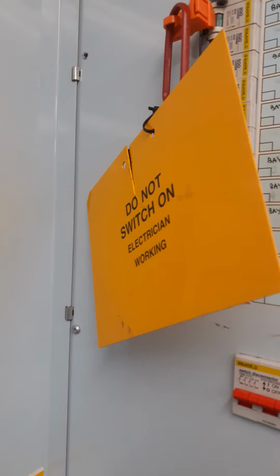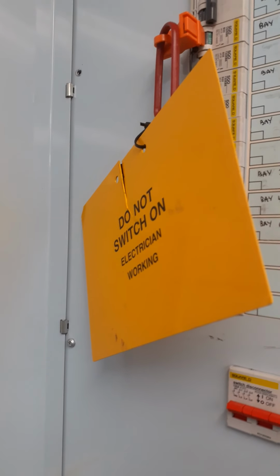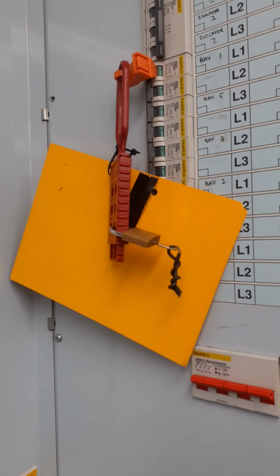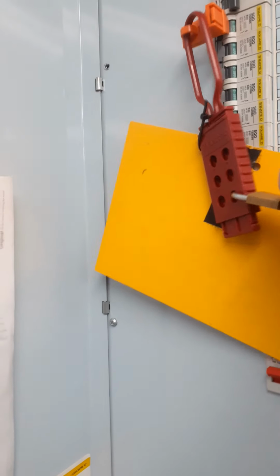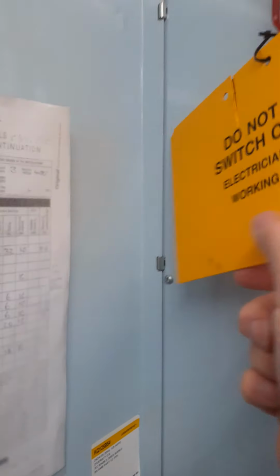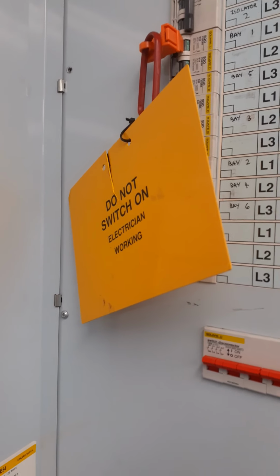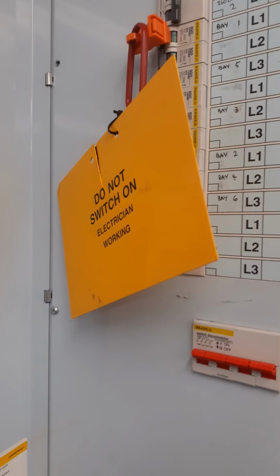The multi-lock then has to be closed. Close the multi-lock like so. A sign is then added through the multi-lock, so to warn everybody not to switch the circuit on, and then each person working on the circuit adds their own lock. So the lock is then fitted, and then all importantly the key is kept with the user. Sign should be turned around so it can be displayed. Now that is the circuit identified, switched off, locked off, and a warning sign placed.